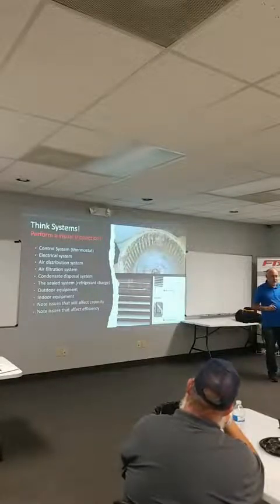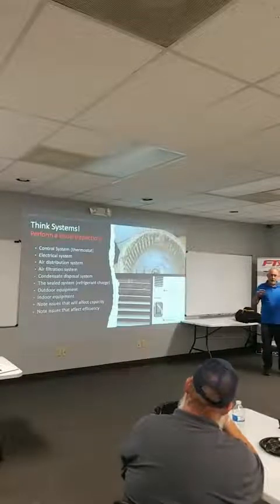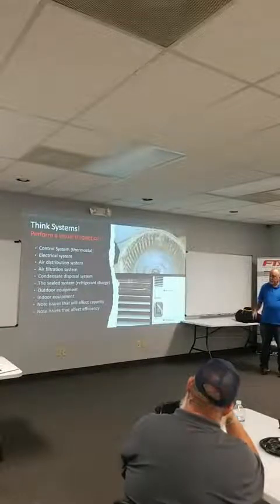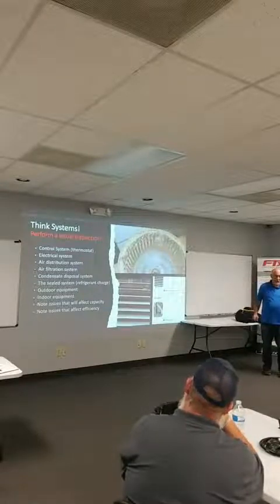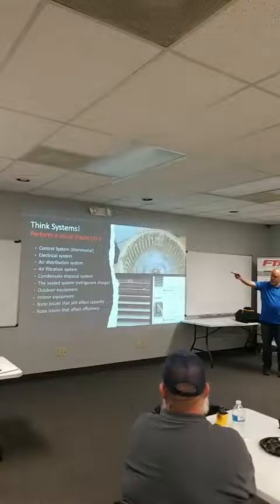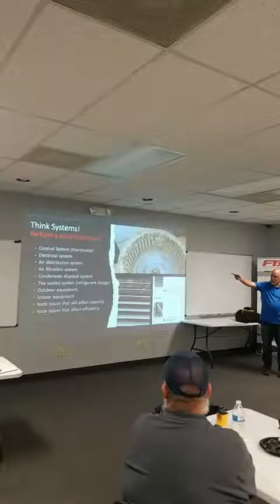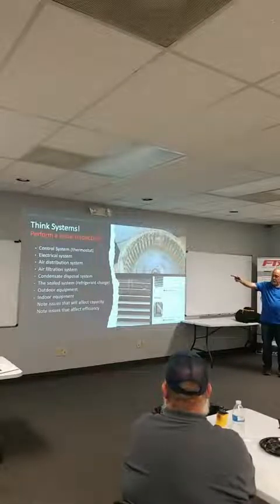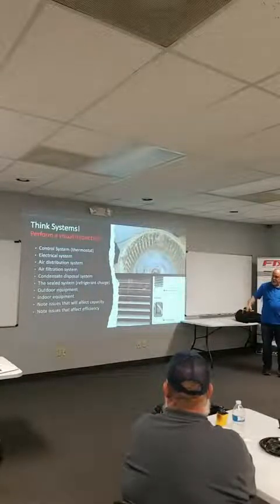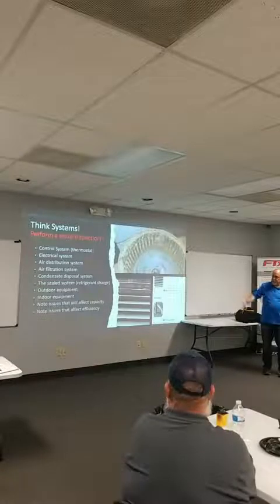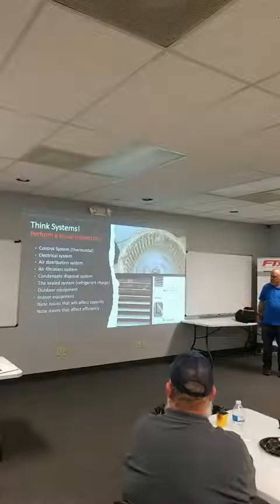And this is the biggest change in my mentality when I got into doing this for a living. First of all, we have a control system, right? The most basic control system is just your thermostat, right? Now you can have a control system with safeties, and you can have other controls, but we got a low voltage control system. We have an electrical system that provides electric to that unit. We have an air distribution system that distributes the air. We have an air filtration system that filters the air. We have a condensate disposal system that gets rid of the condensate. We have a sealed system that our refrigerant flows around in, right? And we have our outdoor and indoor equipment and, you know, any notes that would affect efficiency and capacity.